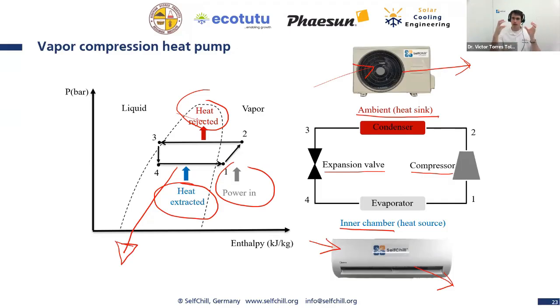What about if you are compressing vapor? Then we are able to condense this vapor while releasing heat, while getting cooling energy, and be able to have a stable temperature. This will be very nice, right? Because then you don't have to go to higher temperature. So let's have a look at this. If we have the compressor here and we are compressing vapor, and this vapor is, so to say, at 50 degrees, and then we are able to cool down the vapor. Then what's happening? We are cooling down the vapor, but we are at a temperature where this vapor is going to turn into liquid. This is wonderful, right? Because in the phase change we are able to keep stable temperatures, and we are able to get a lot of cooling energy from the ambient or release a lot of heat to the ambient. Very nice, because we have been able to limit the temperature a little bit. So we don't need 70 degrees, we can be at 50 degrees. We don't need to heat up so much.